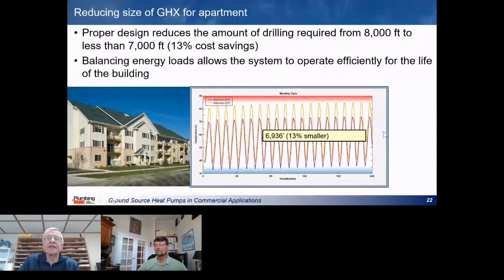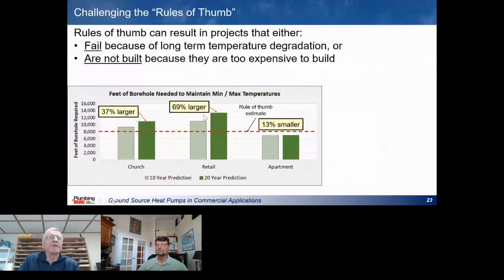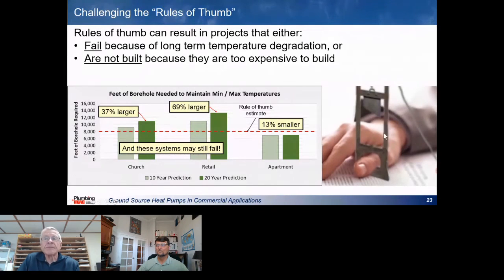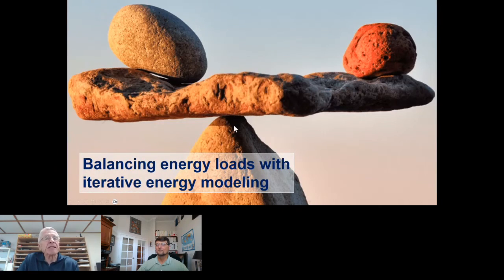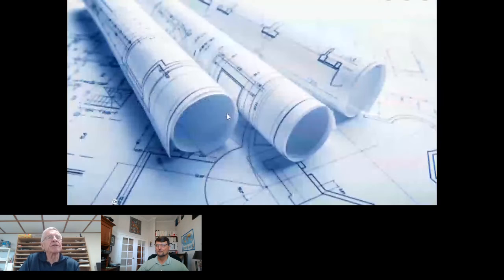Whereas this one can continue on sustainably for the life of the building, because the energy loads, how much heat you're putting into the ground versus how much you're taking out, is going to be fairly even throughout the life of the building. So this one's bigger, this one's bigger, this one's bigger because we're extracting more heat. This one's bigger because we're dumping more heat into it. This one's going to be smaller because we're dumping into the ground, we're taking out the following year. And that means a smaller, less expensive ground loop, which is going to be a lot more cost effective to build. So rules of thumb don't really apply to this industry. And the key is really balancing how much energy you're shoving into the ground versus how much you're taking out.